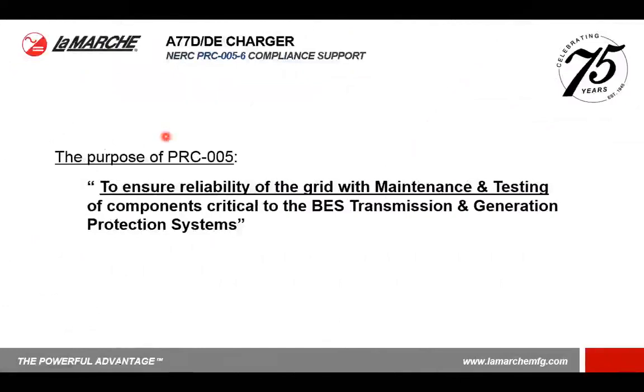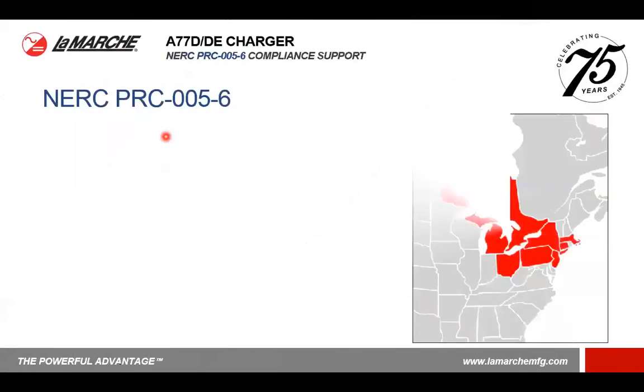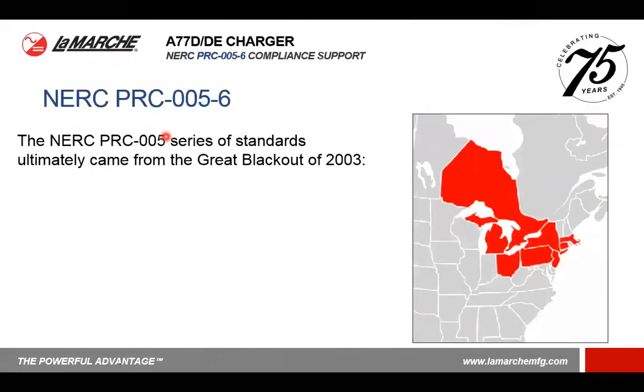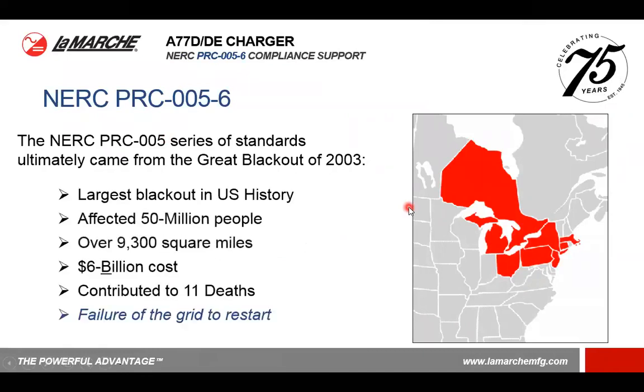So really the purpose of PRC-005 is to ensure the reliability of the grid with maintenance and testing of components that are critical to the BES transmission and generation protection systems. Essentially, this series of standards was ultimately created from the Great Blackout of 2003. This was the largest blackout in US history. It affected over 50 million people, spread over 9,000 square miles. Over 2 days, this incurred a $6 billion cost and contributed to 11 deaths.